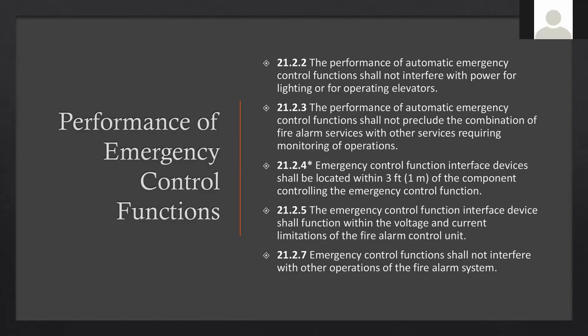Question: what happens if your shunt trip is in a different place from your relay location for the elevator? Answer: that shunt trip relay needs to be moved within three feet of what it's controlling. If you have your primary, alternate, and cab hat over beside your elevator controller, then your shunt trip relay needs to be within three feet of the actual shunt trip — the arm that throws in the room to cut the power.